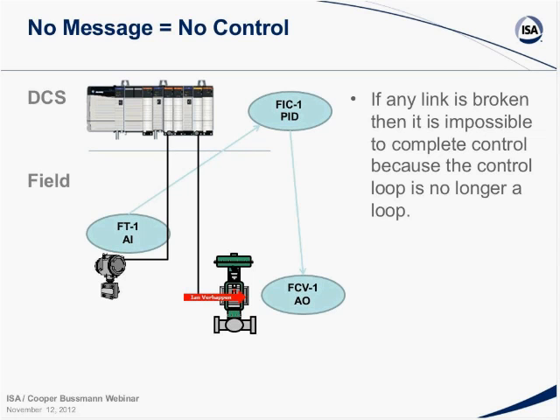So now, if we took that out, if we took out our signal, we wouldn't really be getting it. We cut out the wire, we wouldn't get that signal either to go to the PID. So now what are you controlling to? How do you compare your set point? Everyone kind of takes it for granted that my signal is always going to get from A to B, uncorrupted, 100% accurate, representative of the process.